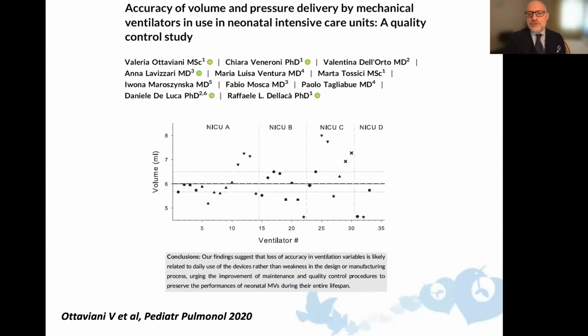So some years ago, together with Raffaele, we did a nice experiment, because we tested the accuracy of volume delivery and also pressure delivery for several ventilators in my NICU, in my lab, and in other NICUs across Europe. To be honest, these tests were done in conventional ventilation, but we have no reason to believe that these ventilators are going to perform differently. And the reason is that at the end of the day, the findings suggest that there is a loss of accuracy in ventilation variables, and this is more or less related to the daily use and the controls that they have been undergoing by the hospital during the use of the machine. So we have to take care of our machines.